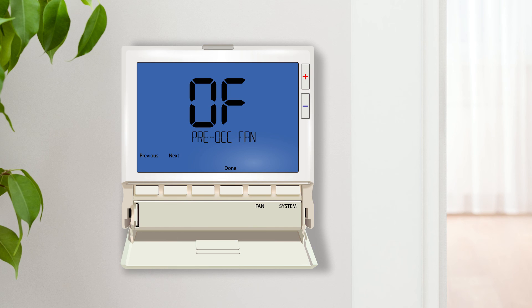Preoccupancy fan circulates the air by running the fan for a period of time before the occupied time period begins. When buildings are unoccupied, the equipment runs less frequently, causing an uneven range in temperature and a lack of air filtration. Running the fan for a period of time before the building is occupied and the system activates can save energy and improve the air quality.